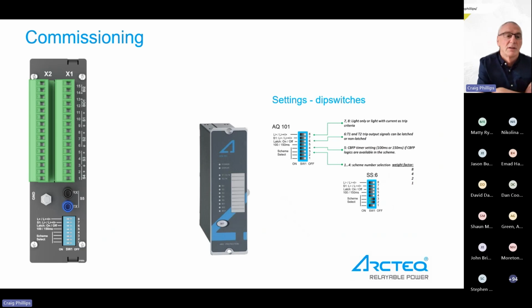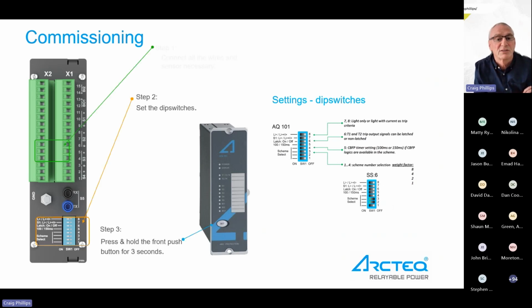Just to show you the rear of the unit and the commissioning approach. You can see there that the back of the unit is easy to wire. It's connection of all sensor wiring to the back of the unit. We configure the dip switches and then we press and hold the set command to commission the unit, and it's self-commissioned within a few minutes if you hold the commissioning button for 3 seconds.